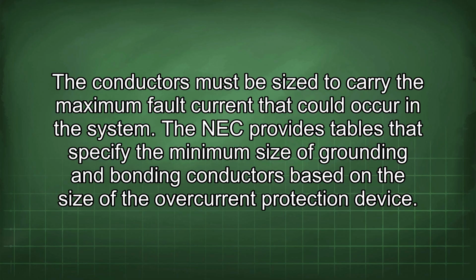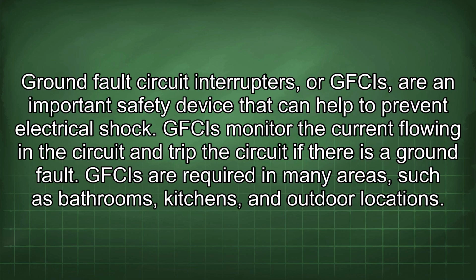The NEC provides tables that specify the minimum size of grounding and bonding conductors based on the size of the overcurrent protection device. Ground fault circuit interrupters, or GFCIs, are an important safety device that can help to prevent electrical shock. GFCIs monitor the current flowing in the circuit and trip the circuit if there is a ground fault. GFCIs are required in many areas, such as bathrooms, kitchens, and outdoor locations.